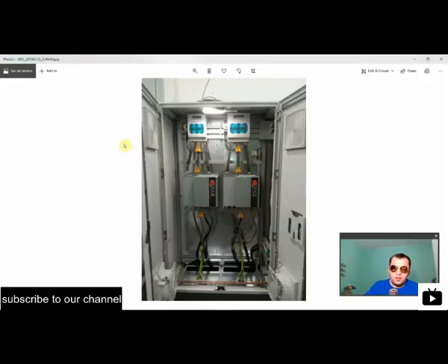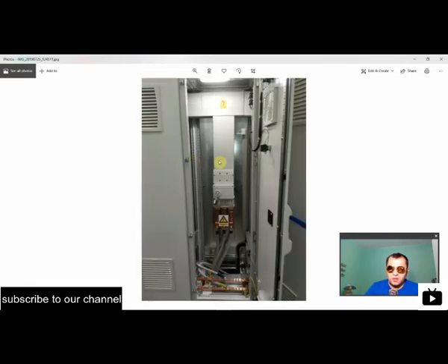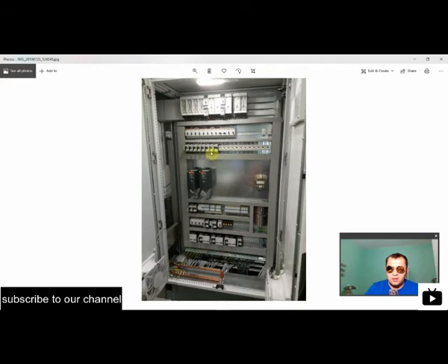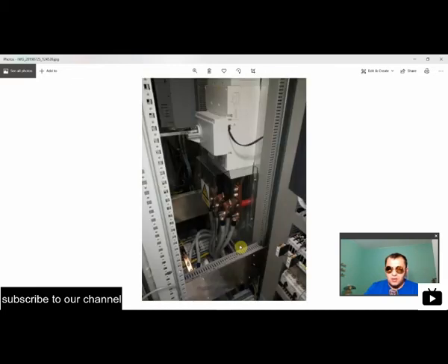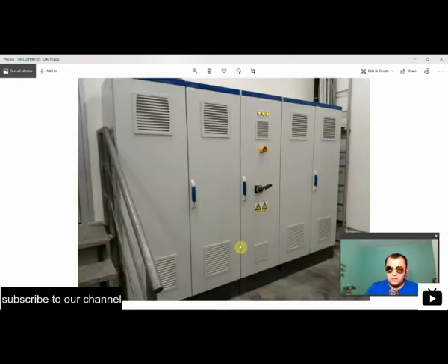As I said, that was a big issue. So for this cabinet, we had to make sure, since we have a lot of busbars and the main circuit breaker, and also for this cabinet, since we have a lot of consumers over here, also the frequency converters, and over here our small soft starters, those were 11 kilowatts. Altogether, we ended up having a lot of fans, so we were able to avoid installing an air conditioning system, which is pretty expensive, and as we've seen during the commissioning, it was definitely a completely acceptable solution to go only with fans.